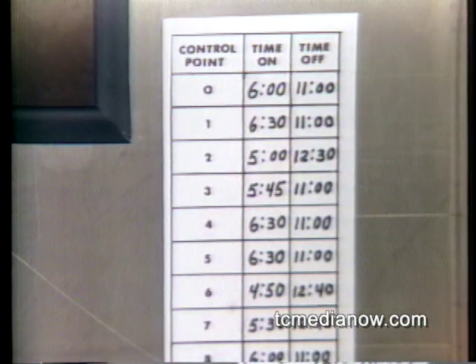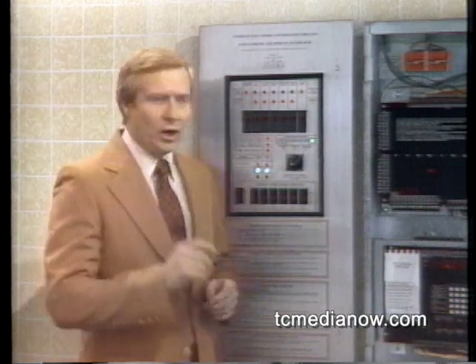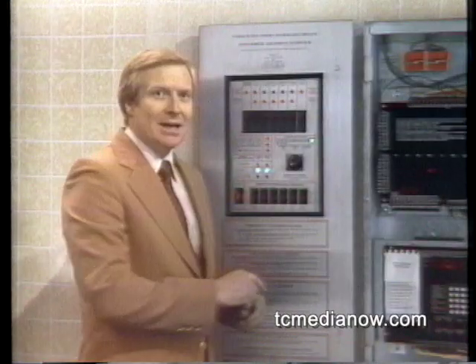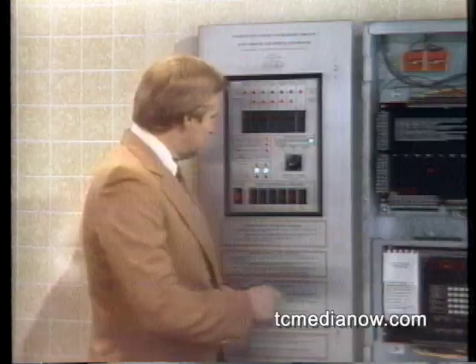Now, an important point to remember is whenever you press the auto load button, you erase any customizing changes you've made to the auto load program. Therefore, every time you press the auto load button, you must also re-enter any custom time cues. The exterior lights may be controlled manually by turning the photocell switch to on, and the lighting switches on or off as appropriate.